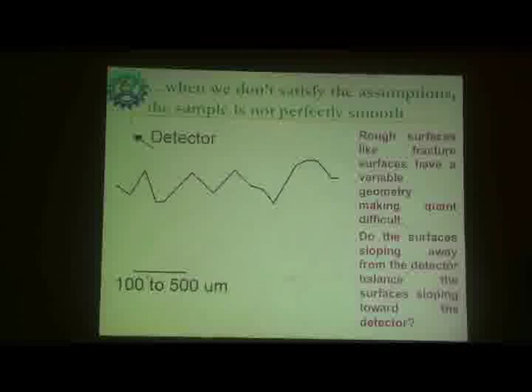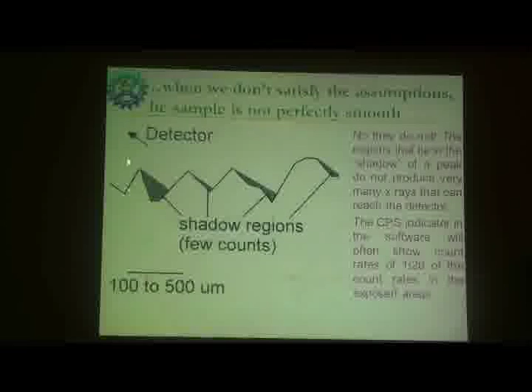There are a lot of problems, because the X-rays may not be coming completely as expected. So some X-rays will be absorbed. The atomic number also will influence the emission of the X-rays, and the fluorescence also will influence the emission of the X-rays. So you have to apply these corrections to get the correct quantification of the composition. So this is the K ratio and this is the weight percentage one can get. And these are the corrections, and the element weight and atomic percentage can be determined.